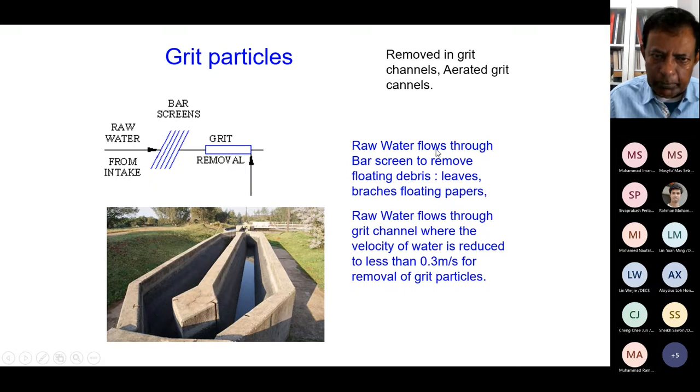Okay, so raw water flows through the bar screens. Bar screens are to remove the larger particles, and they can remove floating debris, leaves, branches, floating papers. All these can be removed in the bar screen. And then raw water flows through the grit channel where the velocity of water is reduced to less than 0.3 meter per second. If you drop the velocity so low, you will be able to remove the suspended solids, okay?